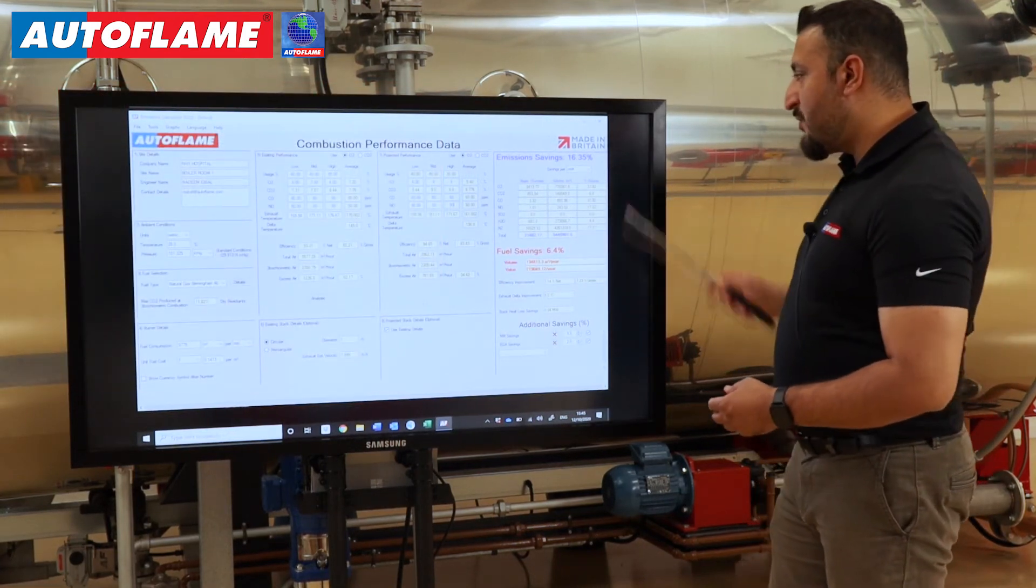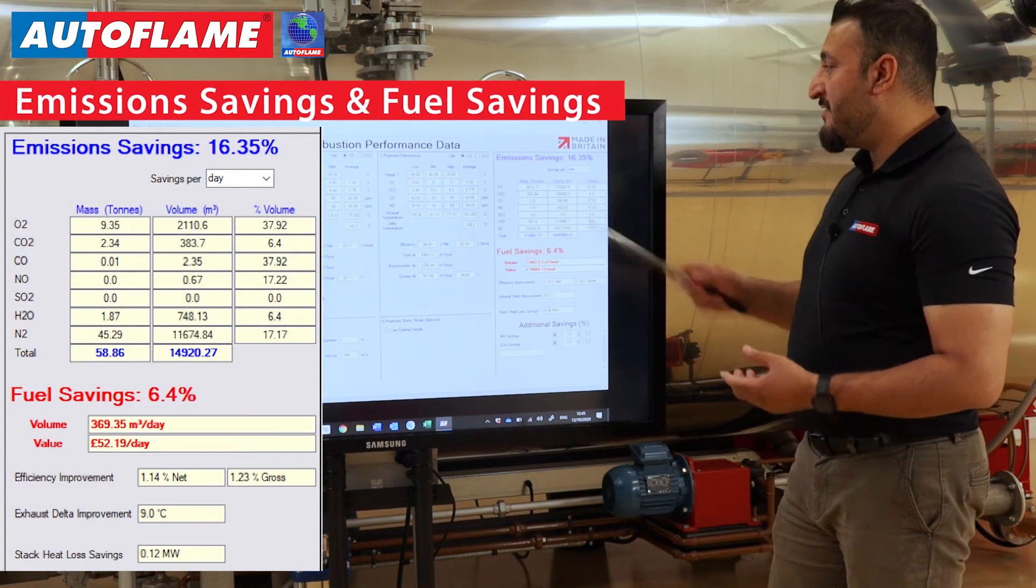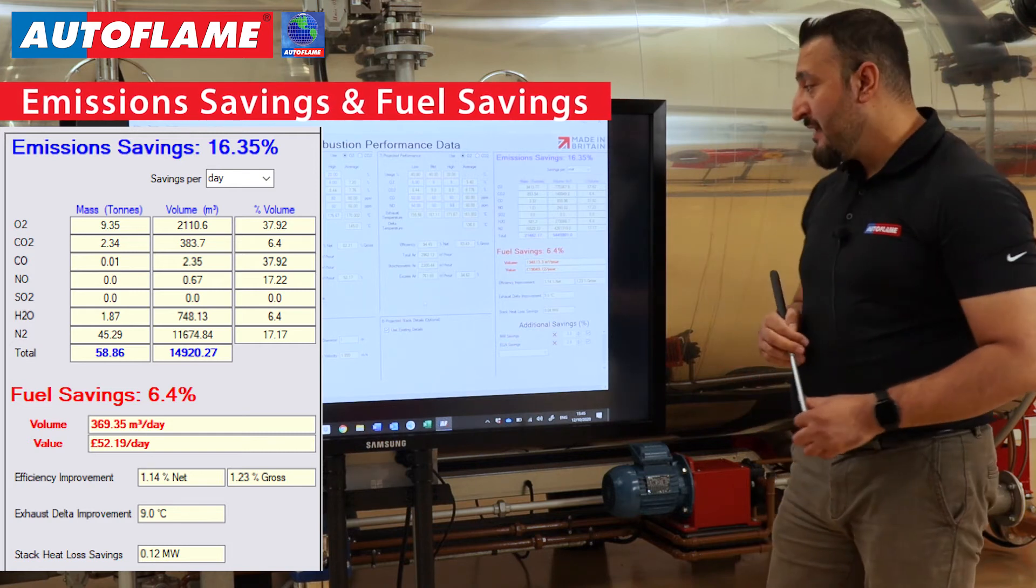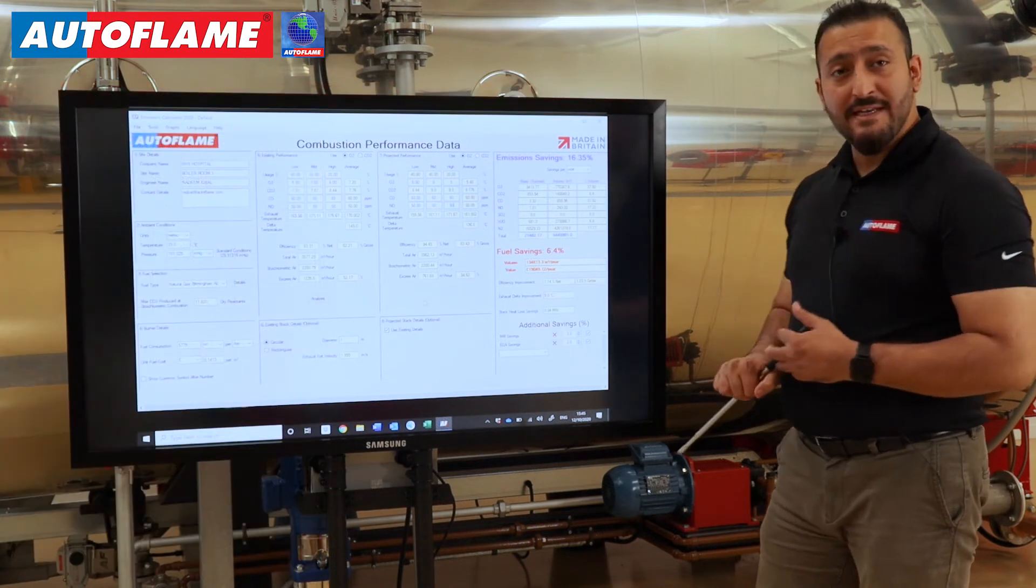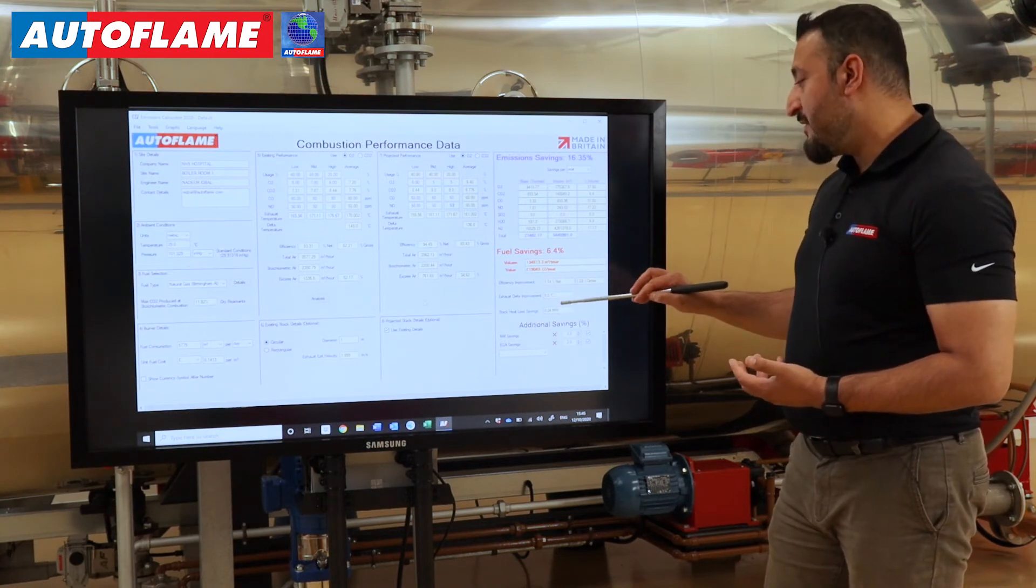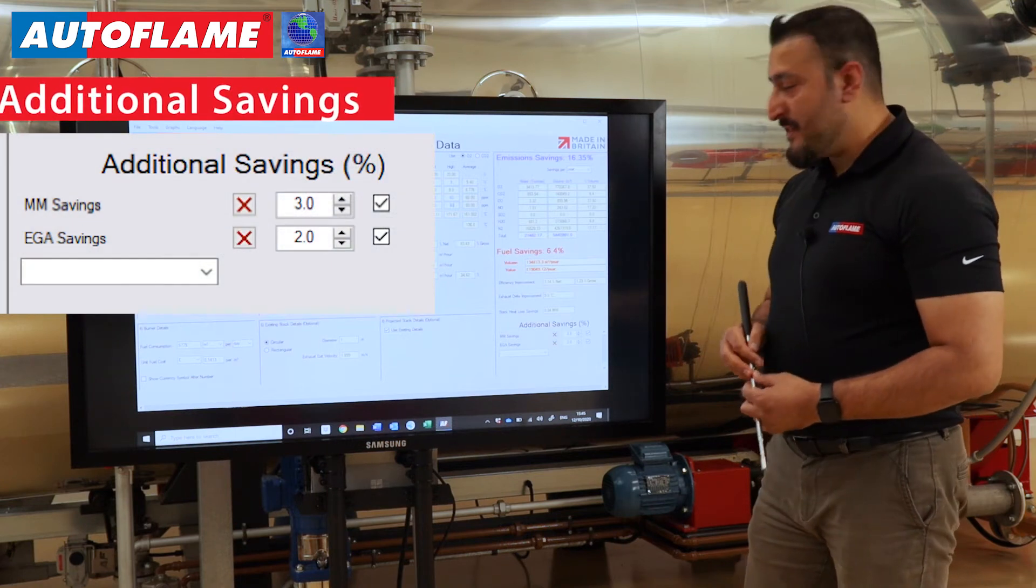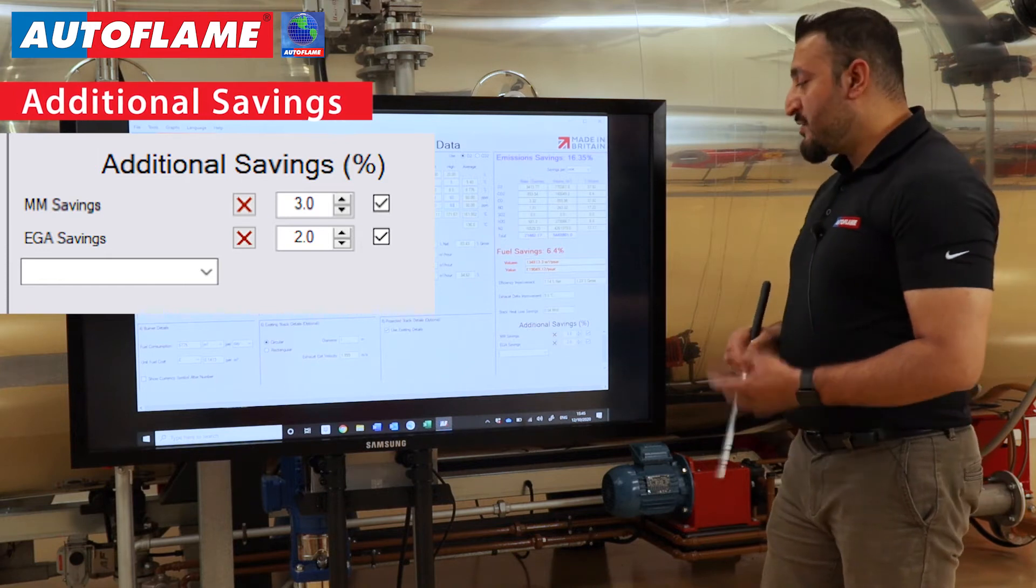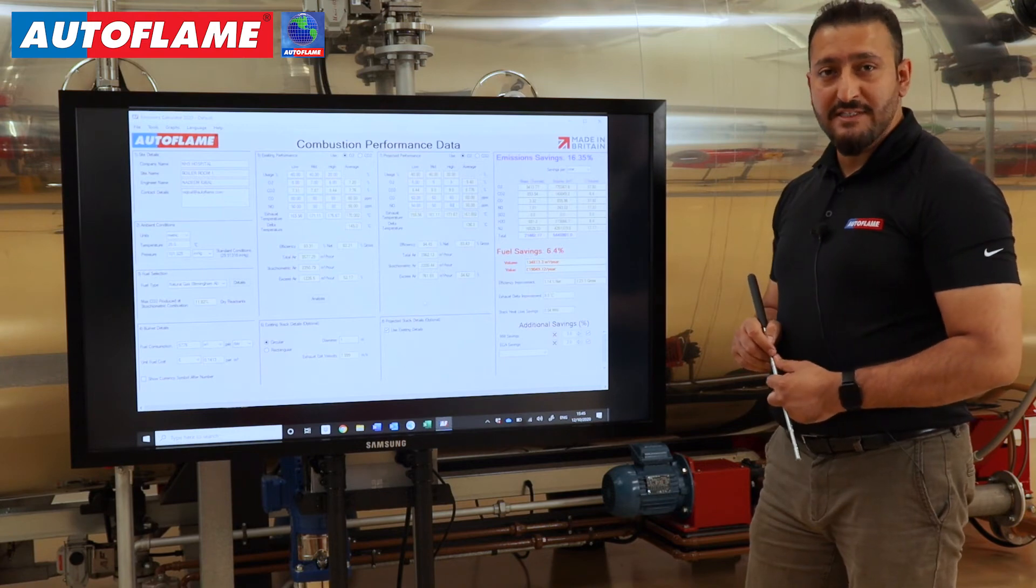At section 8, we are keeping the same stack dimensions because we're not changing that. Finally, on the right-hand side, we can see our savings report. In this particular case, we can see emission savings of 16.35%, which will give us 6.4% fuel savings and overall efficiency improvement of 0.04 megawatts of this particular boiler. We can also add further savings depending on what equipment we're using. In this particular case, we're only adding the MM and the EGA. Exhaust gas analyzer adds further one to two percent of savings with the help of three-parameter trim.